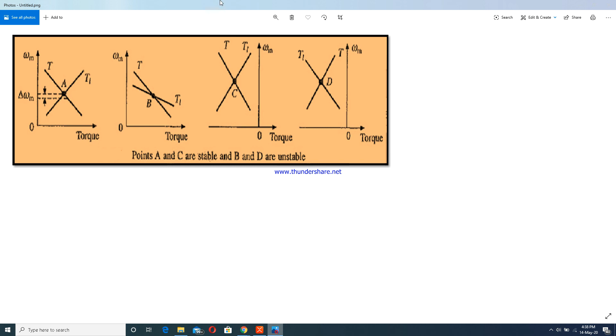Here I have shown 4 operating points A, B, C, D. At operating point A, where your motor torque and load torque are equal, the disturbance results in a decrease in speed by delta omega m. At the new speed you can see motor torque is more than load torque. So, acceleration will occur, and this acceleration will result in the operating point being restored again. That is how operating point A is stable. Similarly, in the diagram that I was showing, operating point C is also stable, whereas operating points B and D are unstable.